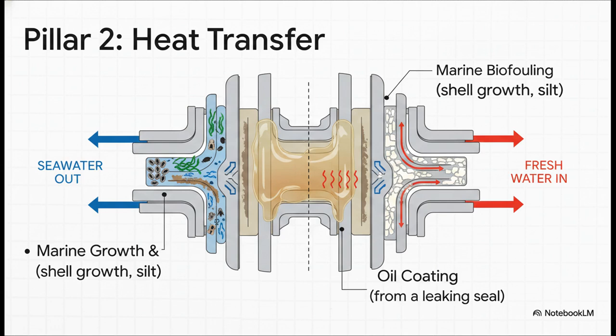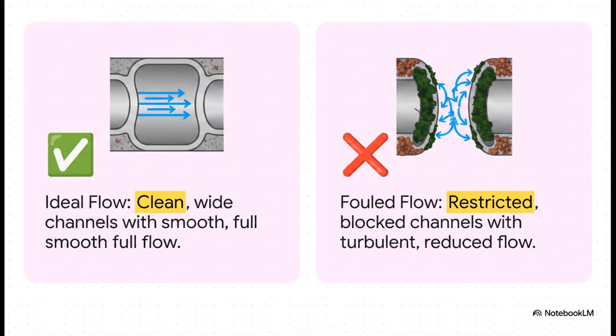And even a paper-thin layer of oil from a tiny leak can act like an insulator, completely crippling the cooler's ability to transfer heat. The heat exchanger is often the silent culprit. And this shows you exactly what's happening inside. On the left, you've got a healthy cooler. The channels are clean, wide, you have smooth, full flow.